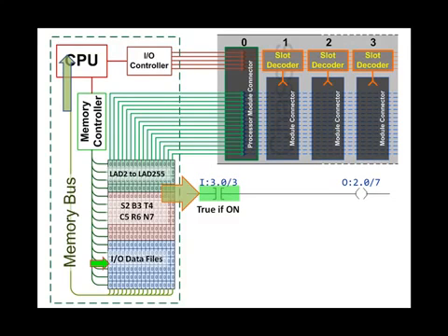If the bit at the memory location is off, then this instruction is false. If the bit is on, then the instruction is true. We will assume that the bit was on when the input module was scanned, and it is highlighted as true. The logic is solved from left to right. So the processor looks at the next instruction.